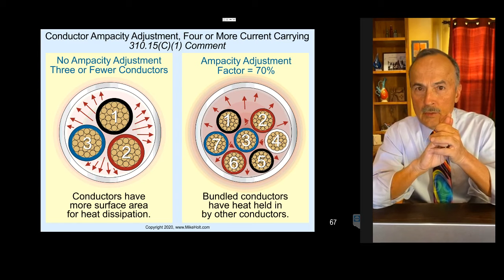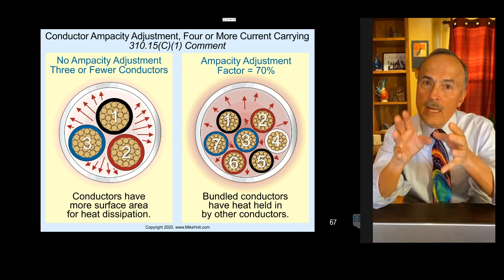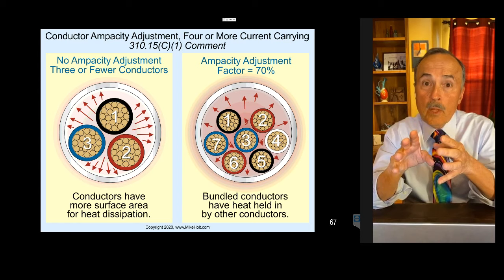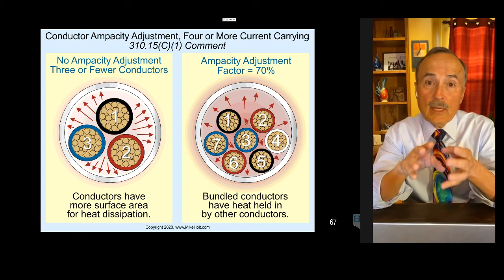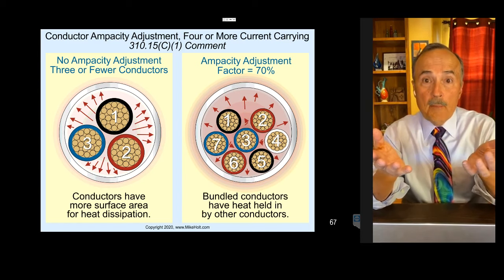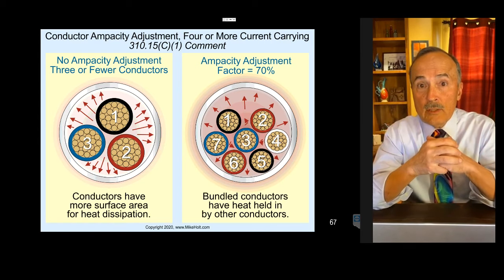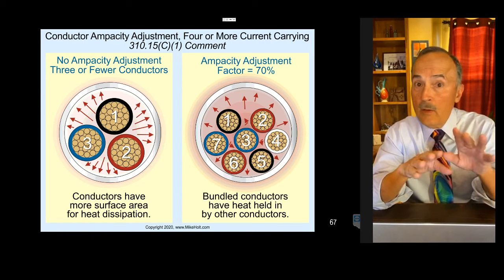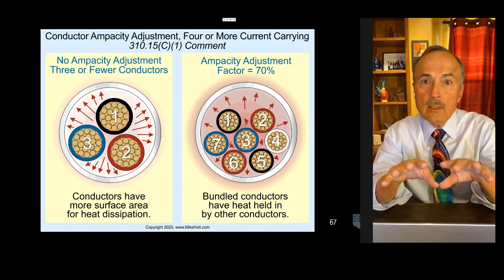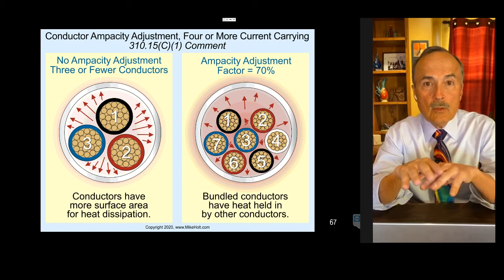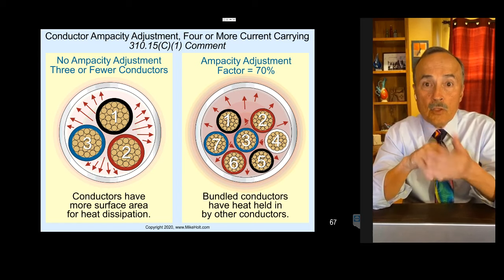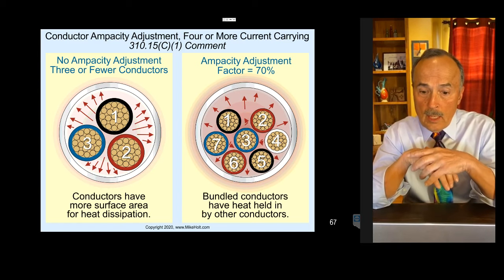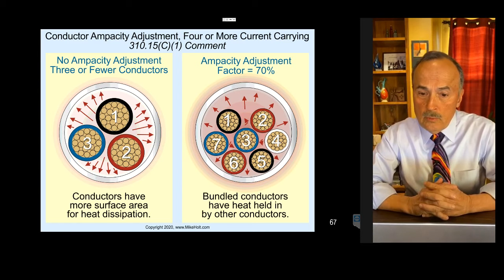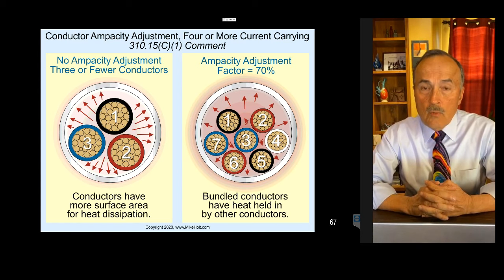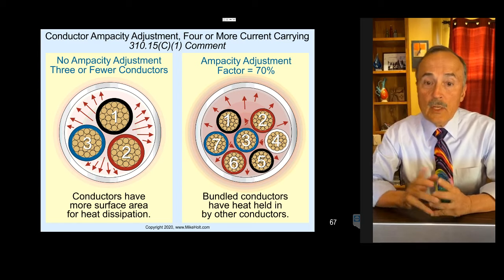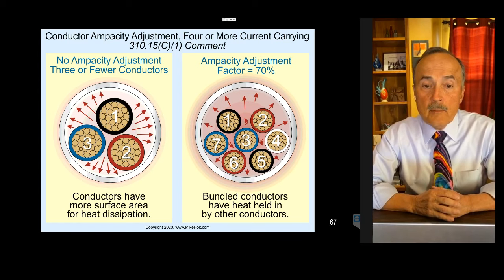Why is this? This is because if you have 3 conductors, and if you go to Table 310.16 or 310.15(B)(16) in the 17 code, and if you read the notes and the rules in there, it says that for 3 conductors there is no adjustment factor. That's because the way the table was designed, the ampacity was based on 3 conductors within a raceway or a cable. So those are the ampacities. If you go more than 3 conductors, then we have to adjust the ampacity. We don't derate, we don't use that word, okay? That's for another group of people. Those are the guys we're not going to talk about.